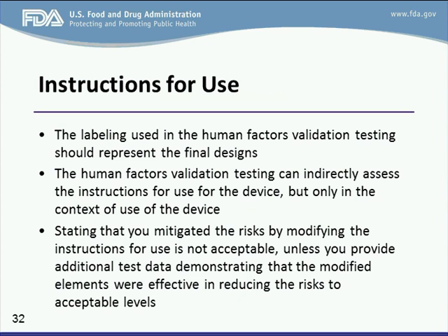So next one, regarding the instructions for use and labeling material. As we mentioned, labeling and IFU is considered as a part of the user interface of the subject device. All the labeling, the IFU, and packaging, when they are used in the human factors validation testing, they should represent the final design.